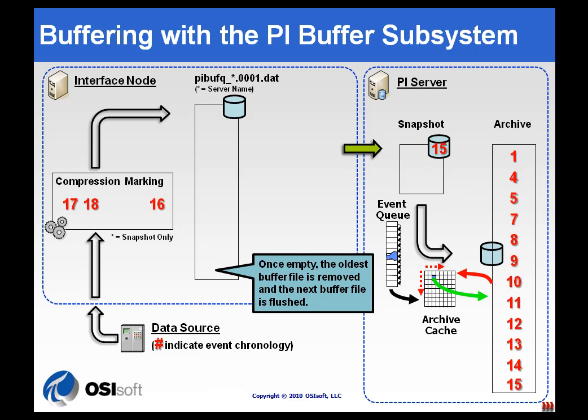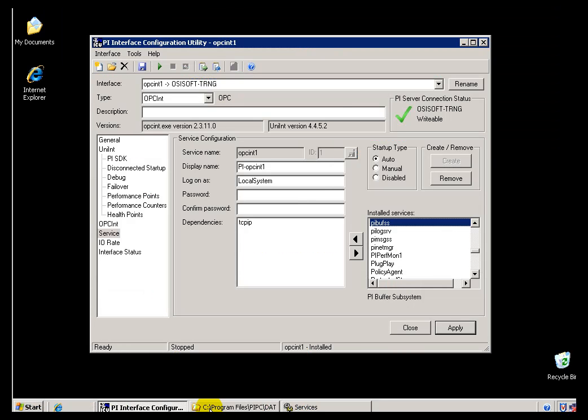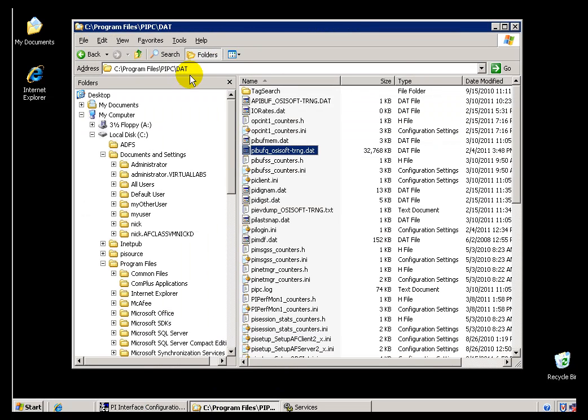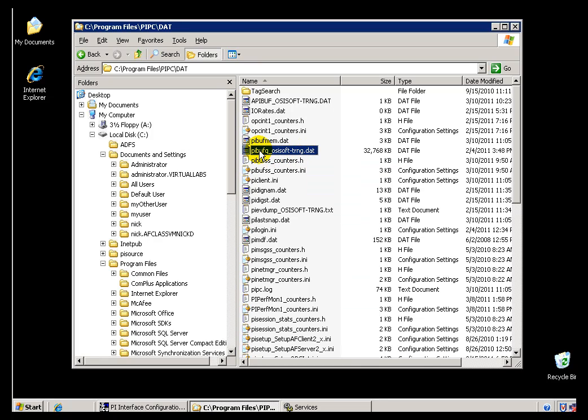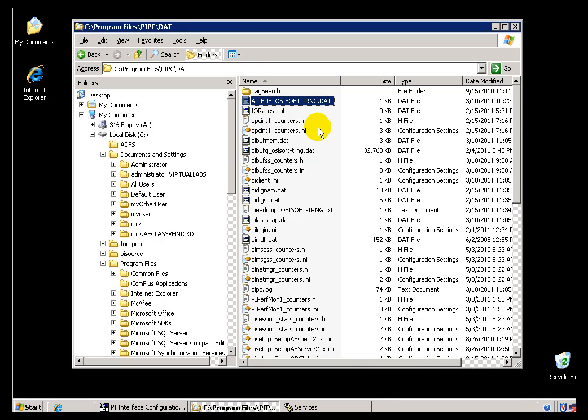Even without any problematic events occurring, if you go into the Program Files PIPC/dat directory, you can actually see the PIBUFFQ file. That's the file that fills up first if the memory queue fills. If that one fills before we've had a chance to empty it, we create another one and append numbers at the end. The name is PIBUFFQ underscore, then the name of the server — for example, OSISoft Training — dot dat. With the older API Buffer Server, there's a similar file called APIBUF underscore, then the name of the PI Server.